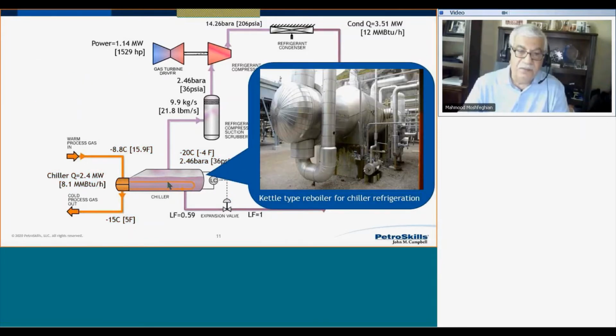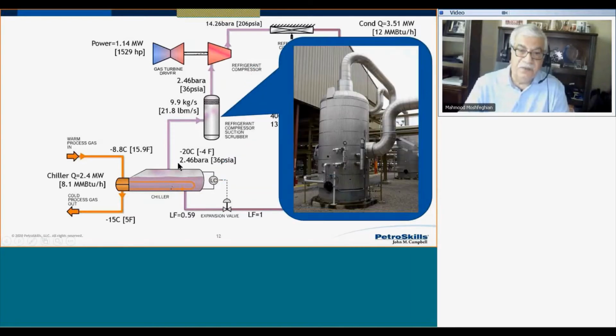The next item of importance in this process is the chiller. As you see here, it is a kettle type boiler, and liquid propane vaporizes on the shell side, outside the tube bundle, removing heat from the process gas. So the propane leaves as saturated vapor at a temperature of -4 degrees Fahrenheit and 36 psi. From here we go to the scrubber. The purpose of the scrubber is to prevent any liquid carryover to the compressor, so the compressor doesn't get damaged.